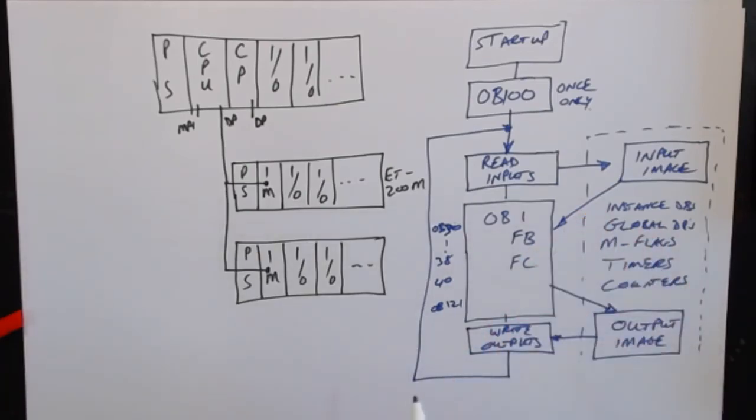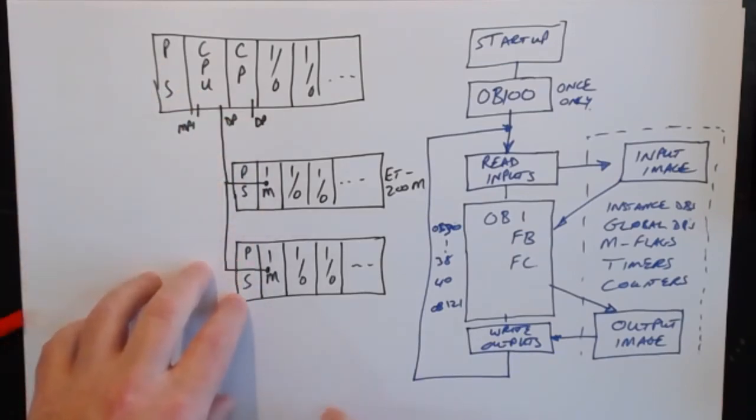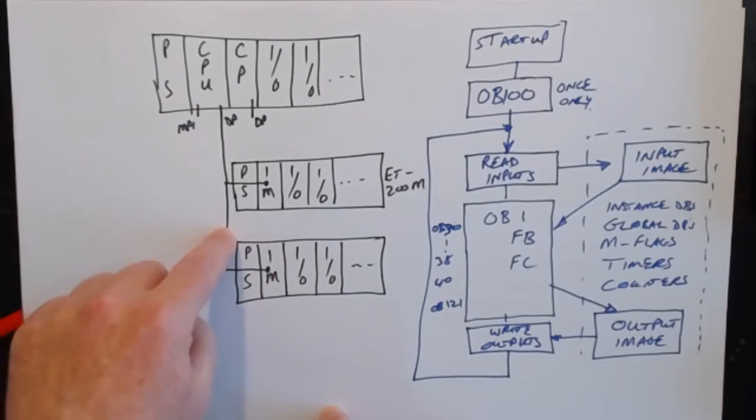And that's how the program operates. But there are several places where we've got issues with this. We've got distributed information across this Profibus cable. If the Profibus cable snaps anywhere, you lose that station. You have a bus fault and you could potentially lose your entire bus.